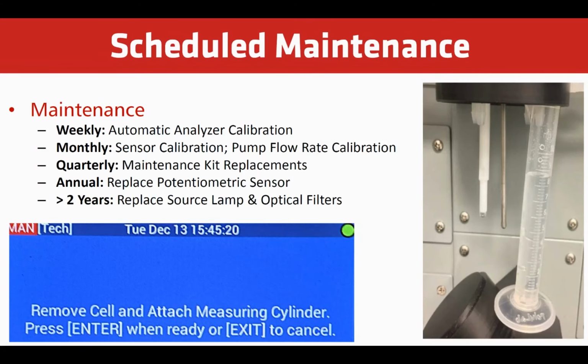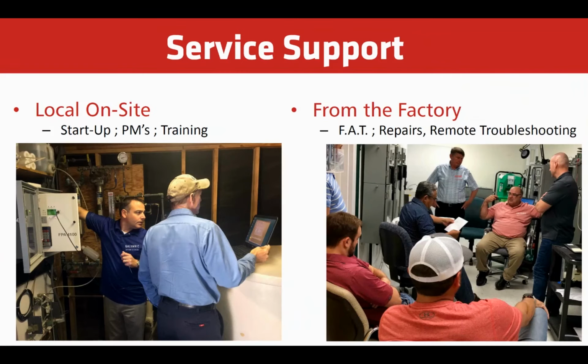Quarterly maintenance, we offer maintenance kits, and that would typically be the peristaltic tubing for the pumps. We replace that and also replace the piston pump seals, and also some of the associated O-rings and gaskets on the sample reaction cell cup. Annually, we like to have the potentiometric sensors replaced or as needed. And every 2 years for the colorimetric analyzers, we would have you replace the source lamp and the optical filters on the detectors. So we offer, obviously, service and support, either local on-site or FATs at our factory.